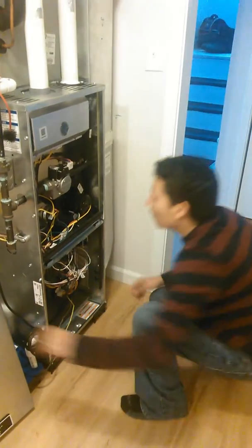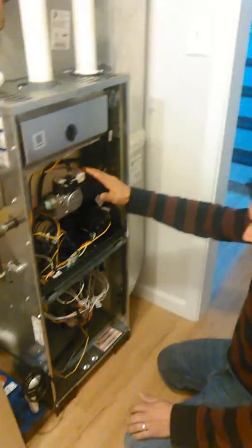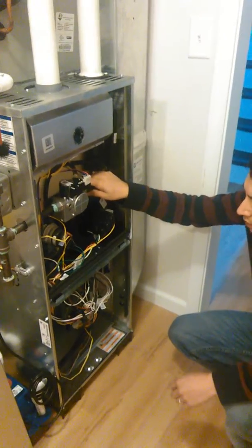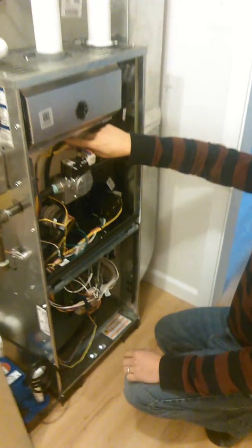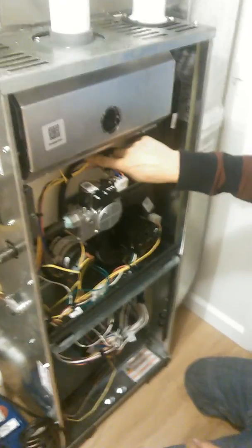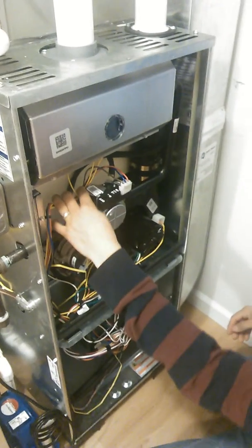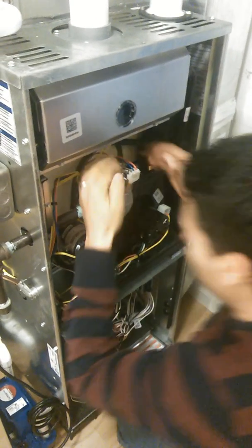As you can see, we've got our heating components over here. The first thing you're gonna check is by using a multimeter. Right up here we have a device called a limit switch. My finger is pointing right there, and what you're gonna do is remove those two wires. It doesn't matter which one — you can remove one wire or both.